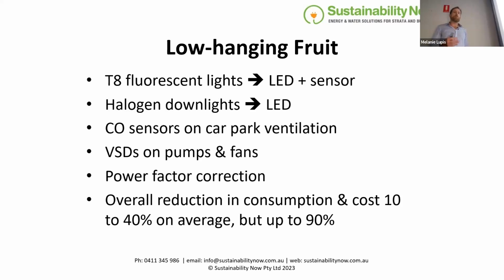So again, we talked about T8 fluoros - in fact, I think these things here could be T8 fluoros. T8 just means tubular, 8/8 of an inch in diameter - it's an old American lighting standard, so they're 25 mil tubes, the old ones you used to see around. If you've still got those, or even T5s, the more modern version, skinnier at 5/8 of an inch diameter, upgrading those to an LED with an integrated sensor is easy. Just replacing a T8 with an LED gives 60% savings automatically. Add the sensor, and if it's in a fire stair, 90+% savings.